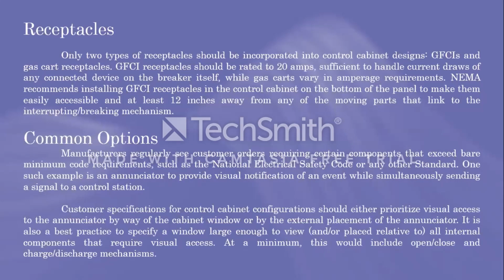So receptacles. Only two types of receptacles should be incorporated into control cabinet designs: GFCIs and gas cart receptacles. GFCI receptacles should be rated to 20 amps, sufficient to handle current draws of any connected device on the breaker itself, while gas carts vary in amperage requirements. NEMA recommends installing GFCI receptacles in the control cabinet on the bottom of the panel to make them easily accessible, at least 12 inches away from any of the moving parts that link to the interrupting or breaking mechanism.